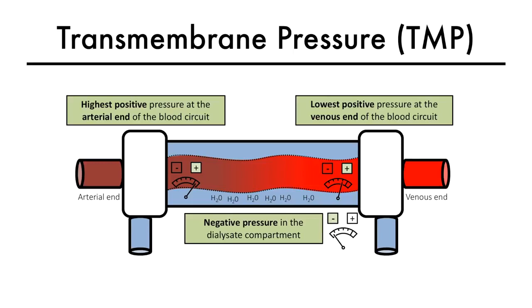In the older dialysis machines, transmembrane pressure was manually calculated by the dialysis personnel based on goal ultrafiltration needs. In modern dialysers, this pressure gradient is automatically calculated and generated by the dialysis machine based on volumetric control of ultrafiltration.